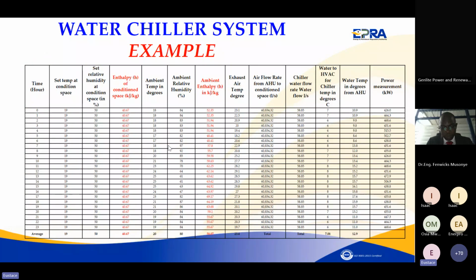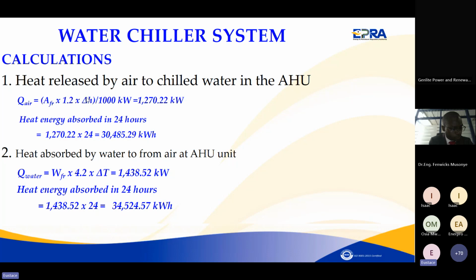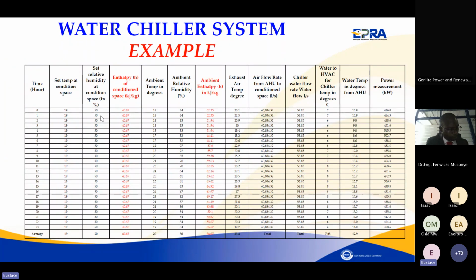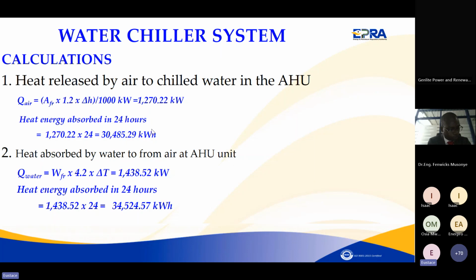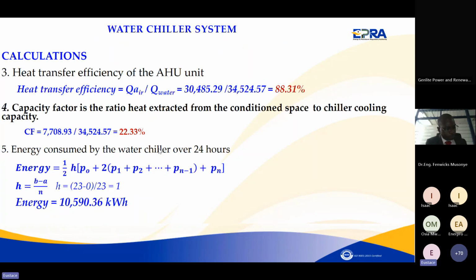Because that one is calculated between the temperatures of the air, the controlled temperature, and the exhaust temperatures. You can see the exhaust temperatures. That's where you get the airflow and this temperature difference, and you calculate that using the same formula as for this, except now the change in enthalpy will change into the change in temperature, because the air going out is at the same relative humidity as this if it's a data center. But if it was a disco hall or a hall where people are eating, where there is a population, you can establish that. So that's why you need to establish clearly the process which is going on. So like now you can see the capacity factor of this one is very low. So this one can raise a red flag, and it's going to be the question.